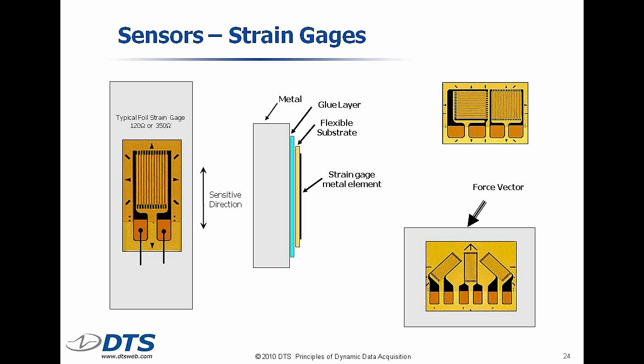So why don't we just put an ohm meter on the thing? Well, it turns out that strain gauges change their resistance in very, very minute amounts. So a typical strain gauge would be a 350 ohm equivalent. If you put a lot of stress on there, it might only become 350.1 ohms. Okay? It takes an incredibly good ohm meter to read that. So we don't do it that way. We'll talk about what the right way to do it is.